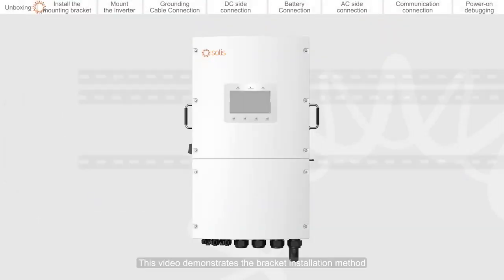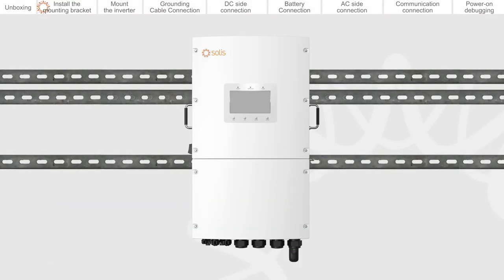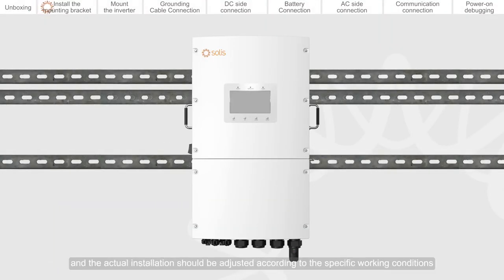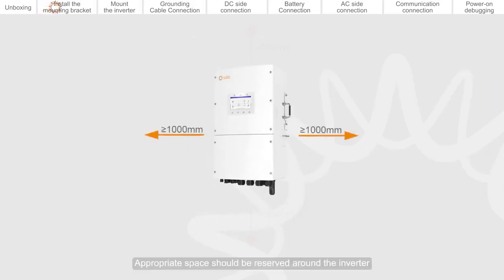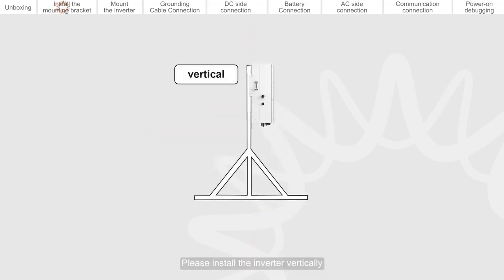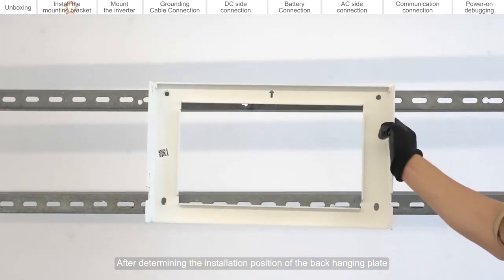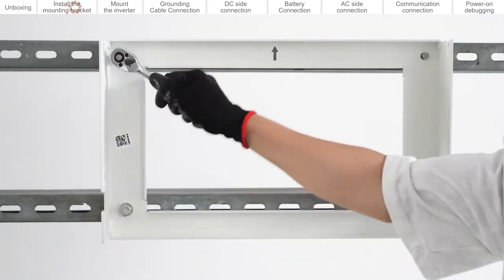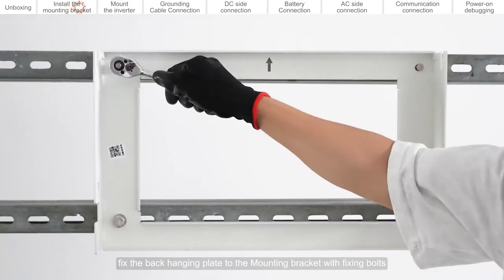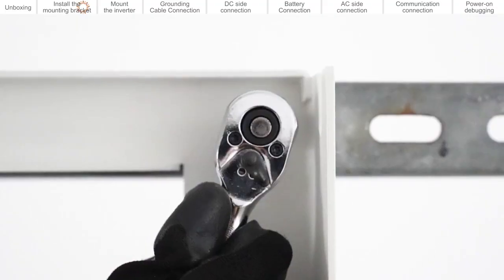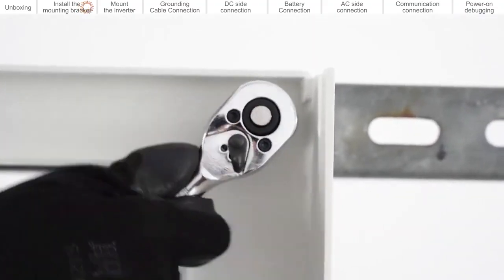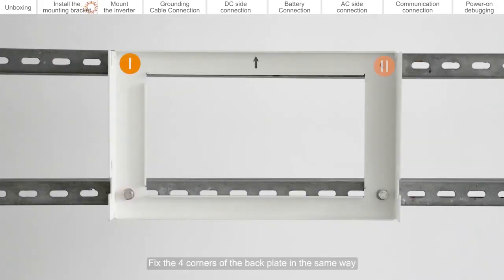This video demonstrates the bracket installation method, and the actual installation should be adjusted according to the specific working conditions. Appropriate space should be reserved around the inverter. Please install the inverter vertically. After determining the installation position of the back hanging plate, fix the back hanging plate to the mounting bracket with fixing bolts. Tighten the bolt with the socket. Fix the four corners of the back plate in the same way.